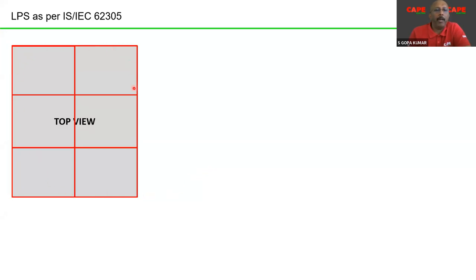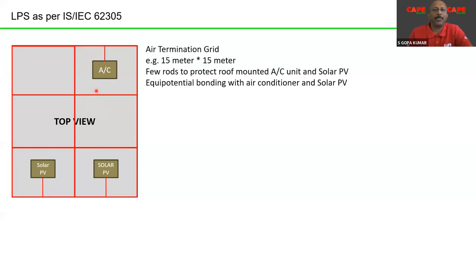So basically, in a simple way, on a flat roof building, the recommended practice is to have a mesh. Let's say, for example, I have made a mesh and there are some electrical items above my mesh, like a solar PV, an air conditioner, a chiller. In that case, I have the option of making equipotential bonding, and probably some rods near the solar PV, maybe two rods near the solar PV and two rods near the chiller, so that these rods avoid direct lightning strike into the chiller. This is a typical case. For example, I made a grid of 15 by 15 meters, with a few rods to protect the roof-mounted air conditioner and solar PV. Equipotential bonding with the air conditioner and solar PV has been made at the top of the building. This is a typical case. So a mesh, some rods, everything interconnected together. This makes the air termination system.